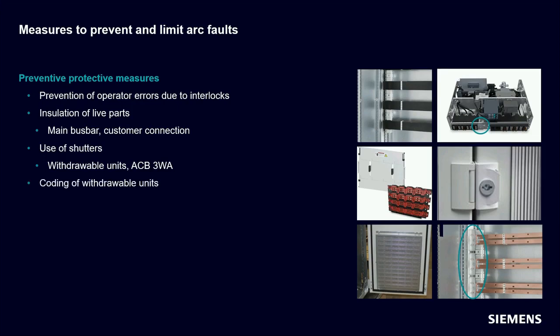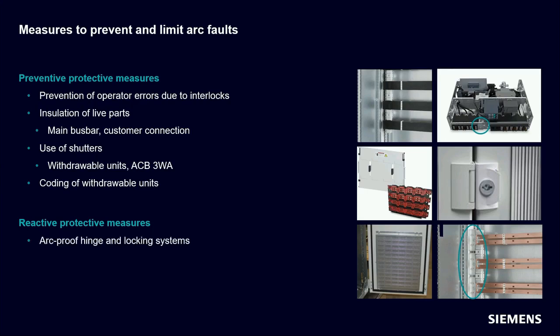Other measures include insulation of the main bus bar and customer connections, the right selection of internal separation, and the use of shutters at the distribution bus bars, adapter plates, or on the circuit breaker. These can prevent live parts from being accidentally touched with a tool during maintenance work. Further measures include the use of coding to avoid confusion between withdrawable units of different ratings. Reactive measures include the arc-resistant hinge and locking system, protective measures at front ventilation openings, pressure relief flaps, roof plates, and arc barriers that prevent the arc from moving from one cubicle to the next.